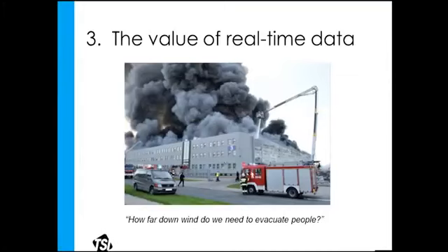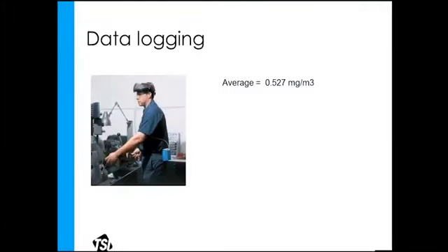And you may not even be calibrated to the right aerosol. It may not matter. We have aerosol above this level. We're at half of the safe level at this point. We need to shelter in place. We get to the dangerous level, we need to evacuate, or vice versa. Whatever your decision making is going to be, you have data to do it.